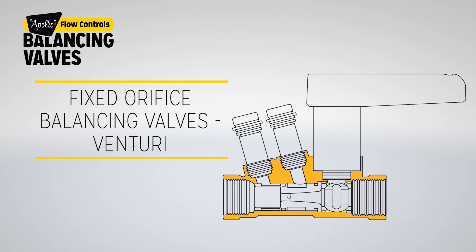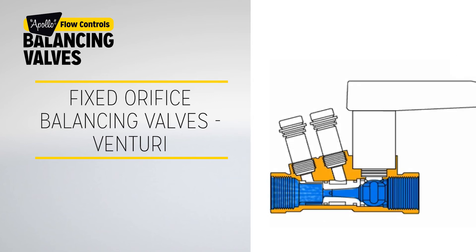Another type of fixed orifice balancing valve is the Venturi. A Venturi fixed orifice double regulating valve uses a Venturi profile instead of a flat plate orifice to generate a measurement signal. This provides less turbulence and significantly reduces pressure loss while improving signal strength.